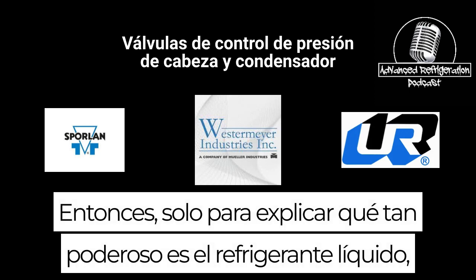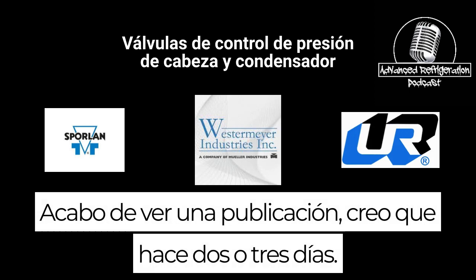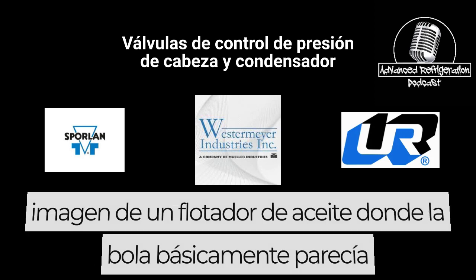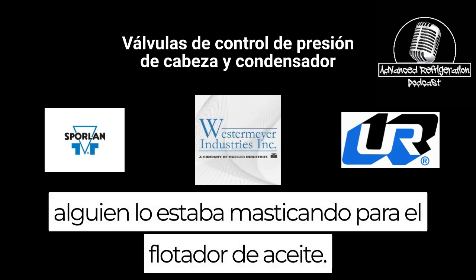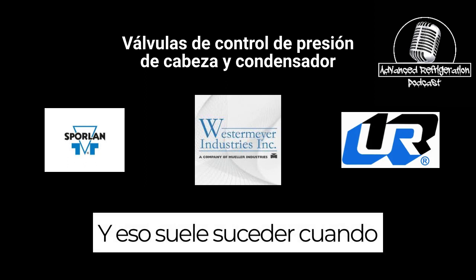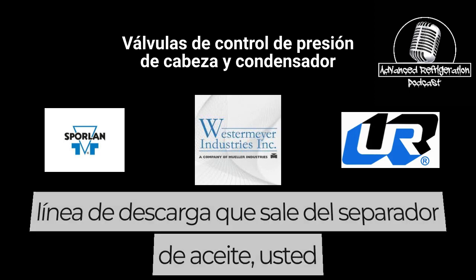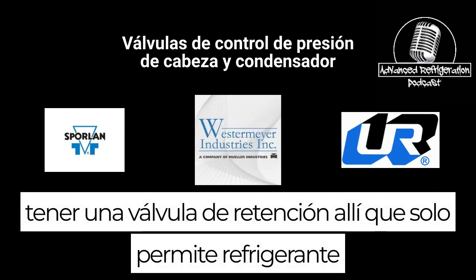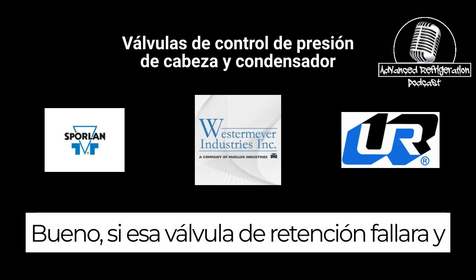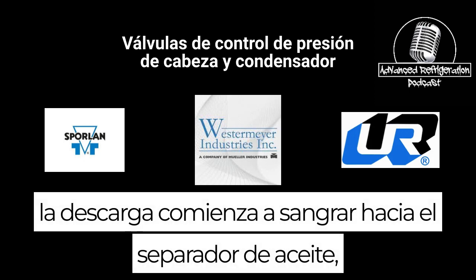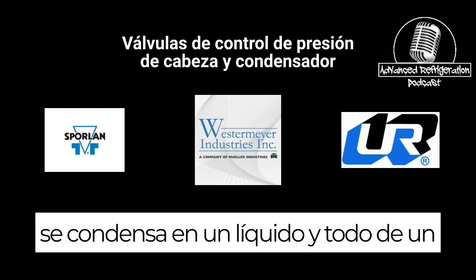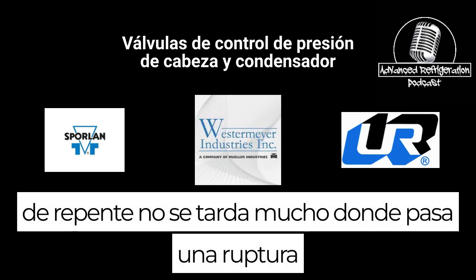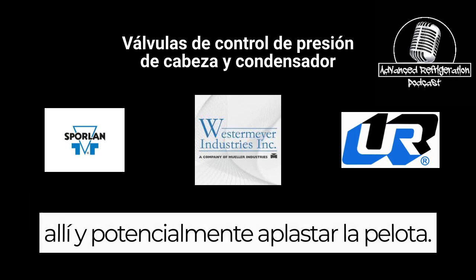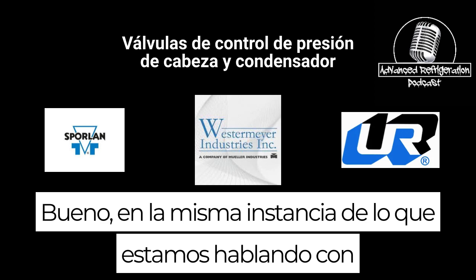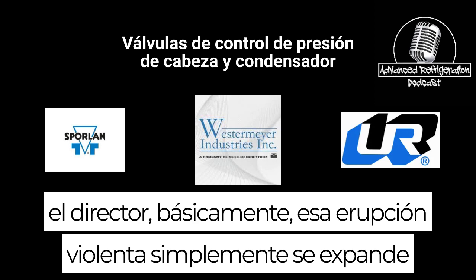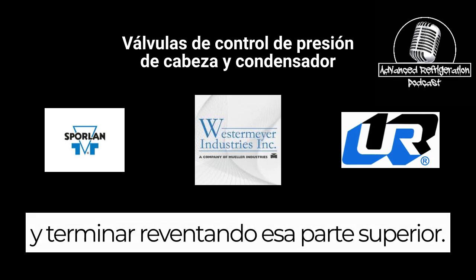Yeah. Just to explain how powerful liquid refrigerant is, I just saw a post two or three days ago on the supermarket tech talk site, where a guy showed a picture of an oil float where the ball basically looked like someone was chewing on it. That typically happens when you have liquid refrigerant bleeding by. If the system is off, typically on the discharge line going out from the oil separator, you have a check valve that only allows refrigerant to go in the out direction. Well, if that check valve happens to fail and the discharge starts bleeding back into the oil separator, it condenses into a liquid, and it doesn't take much for that rupture to happen as soon as you start throwing hot discharge gas into there and potentially crush the ball. Same instance with what we're talking about with the headmaster. That violent eruption expands so dramatically, it has to go somewhere and ends up busting that top ball.